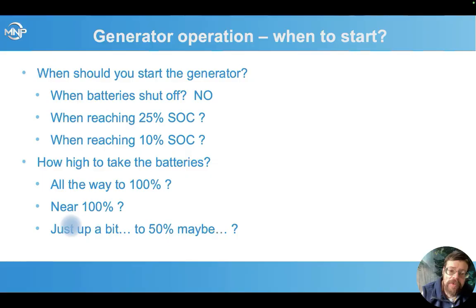How high should we take the batteries? Should we take them all the way to 100%, near 100%, or just kind of do a boost from 25% to 50% and then shut it back off? It depends again on what the situation is. If we're expecting better weather to come back pretty soon, maybe just boosting them up to 50% and seeing how the next day's sun is might be good. If we know that we're in this for the long haul and we don't have much solar input for days, we might as well go all the way back up to 100% and recalibrate that BMS and call it good, because the sun's not going to get there. If we know that we've got a little bit of sun, maybe cloudy conditions, but our array is still producing 10 or 20% of rated capacity, we might go near 100% and then let the solar take it all the way up to recalibrate the BMS.